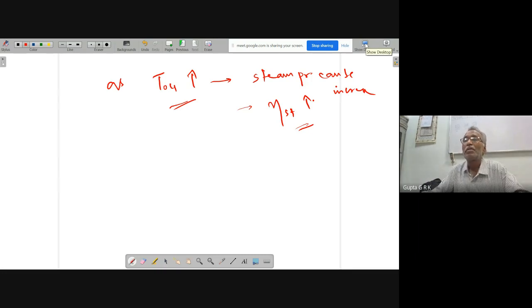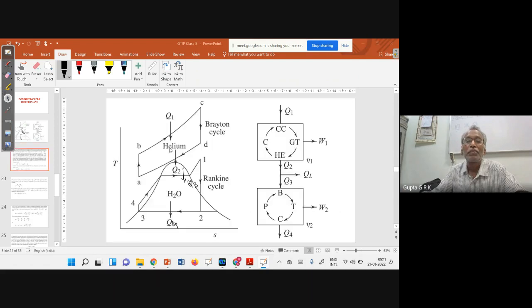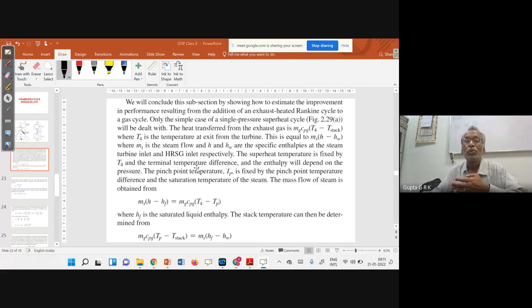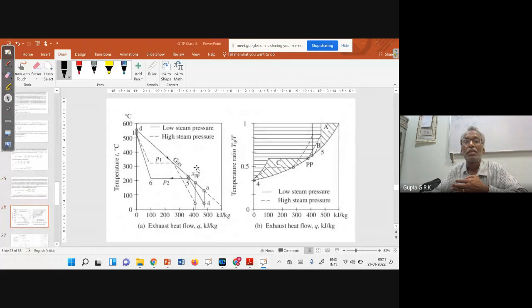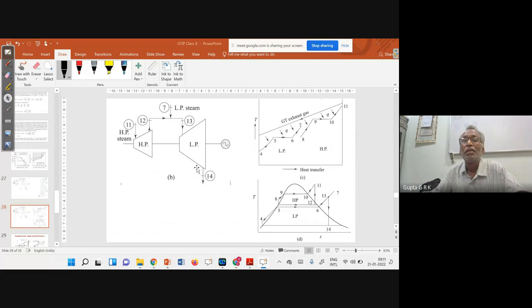And sometimes there is what is called a dual pressure system. So the dual pressure system is something like this. I can show you. This is single pressure. Dual pressure, I can have 2 cycles like this. This is one cycle, this is another cycle. There are 2 steam cycles. One is a high pressure cycle and another a low pressure cycle. And this 4, 5, 6, this one is for the low pressure, and this goes in this way. This is the economizer, evaporator, superheater for the low pressure cycle. And for the high pressure cycle, this is like this, and this goes this way. So you can see that these lines are going near the exhaust gas line, so the heat lost can be reduced. Am I clear about it?